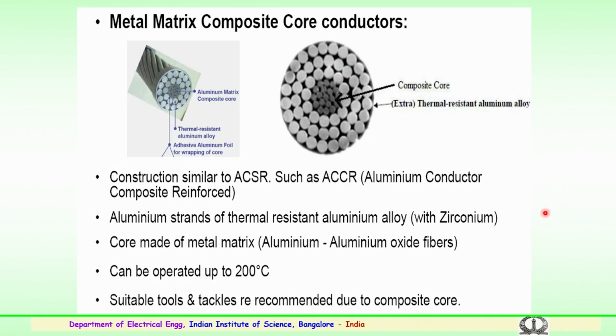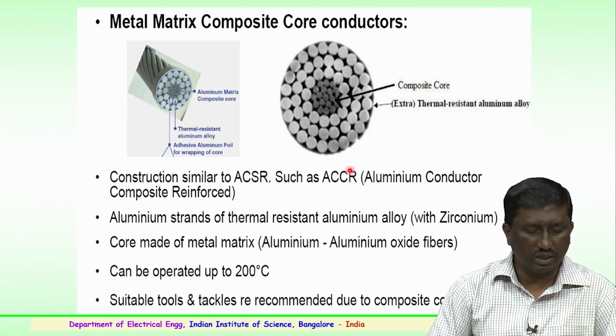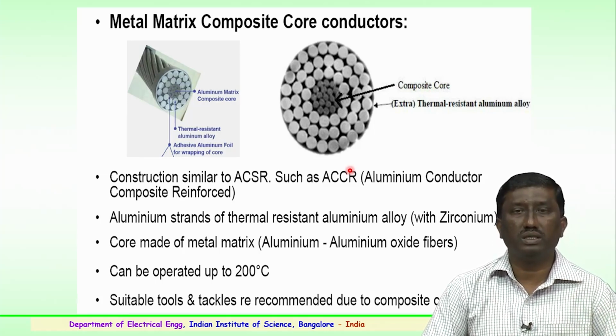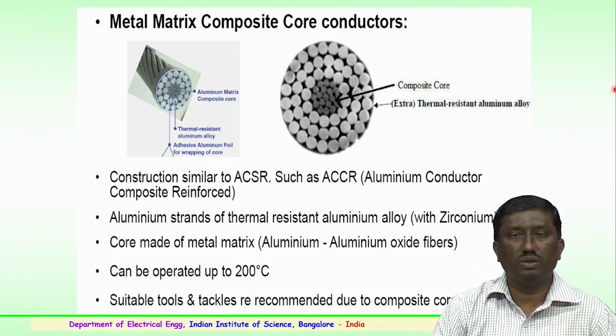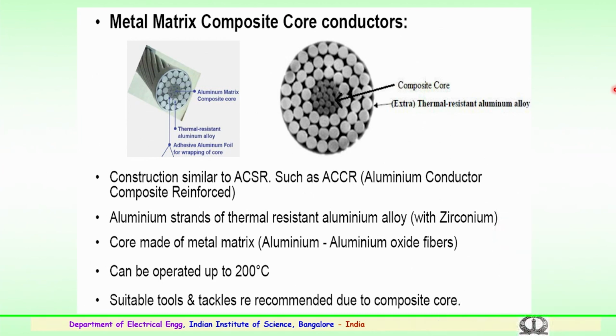The other type of conductor is the metal matrix composite core conductor, where you can see here the aluminum matrix with a composite core. This is the composite core with the aluminum matrix, and these conductors are all shown here with the extra thermal resistant aluminum alloy. The adhesive of the aluminum foil for wrapping the core is also indicated here. So, this is again a special conductor. It is similar in construction to the ACSR conductor and also similar to the ACCR conductor with the composite reinforcement. For this type of conductor, the aluminum strands are again thermal resistant, an aluminum alloy containing zirconium in its composition.